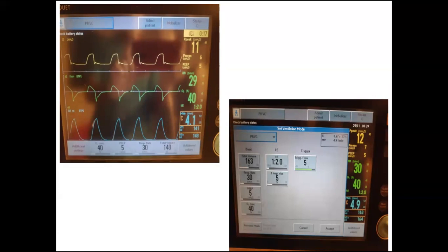That is simple. The name can be different in different ventilators, but the principle is the same. Adaptive controlling is PRVC. You are going to get the desired tidal volume, but what you are controlling is pressure. So you are not controlling volume, you are controlling pressure.